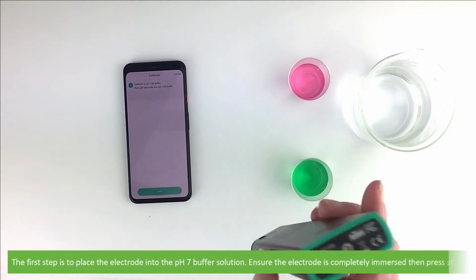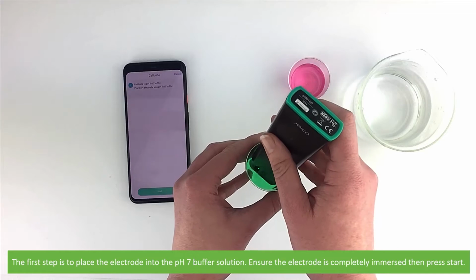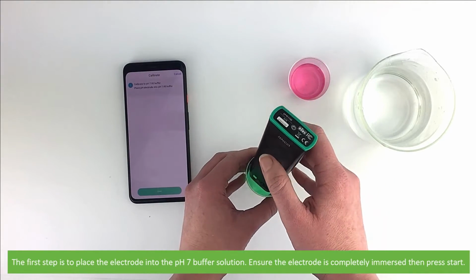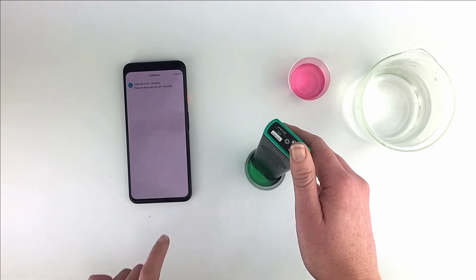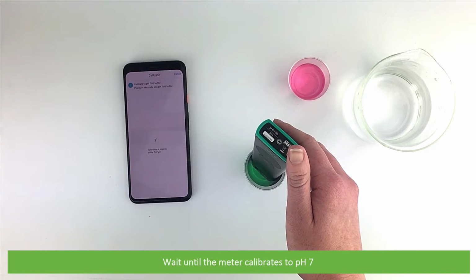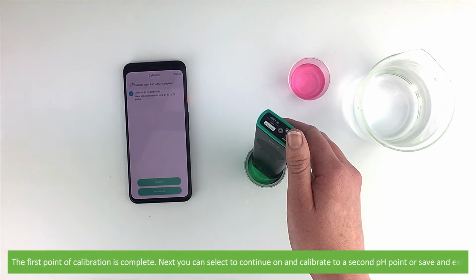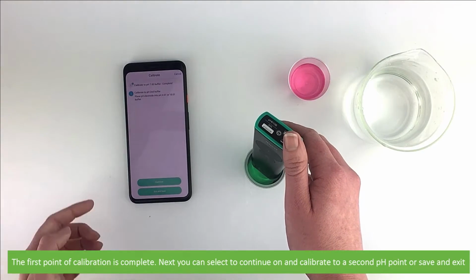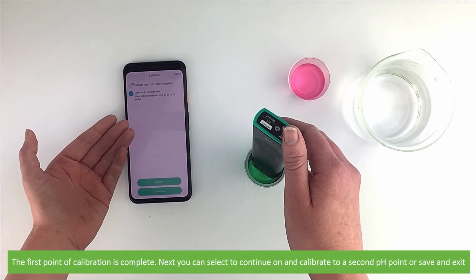The first step is to place the electrode into the pH 7 buffer solution. Ensure the electrode is completely immersed, then press Start on the app. Wait until the meter calibrates to pH 7. The first point of calibration is complete. Next, you can select to continue on and calibrate to a second pH point or save and exit.